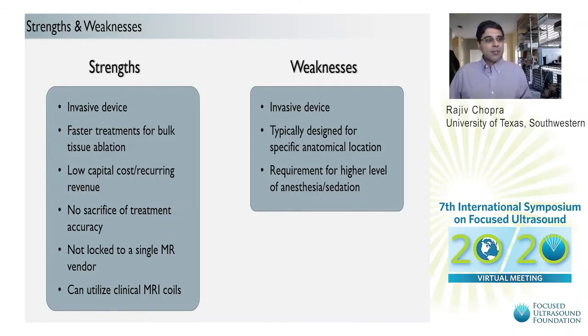These systems tend to have a low capital cost, which is a strength when trying to propose them to a hospital or healthcare environment. And from the other side of the equation, for a manufacturer, there's a recurring revenue because these are disposables, and so every patient has a revenue source associated with them. So that's an interesting strength of the technology. There's no sacrifice of treatment accuracy. We've seen that these devices produce millimeter precision in the body for heating and ablation. So I think that's not really a sacrifice if designed correctly. They're not locked to a single MR vendor, which is also a strength when it comes to trying to expand this to multiple platforms with MRI.